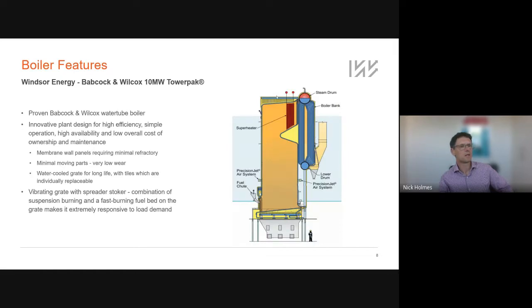This is a typical cross section of what a Towerpak boiler looks like. So the benefits, or the design features probably, of this style of boiler is the obvious one: it's a very tall furnace. The key to a good boiler is getting good combustion, burning out your fuel completely. And the three parameters that allow that are time, temperature, and turbulence.